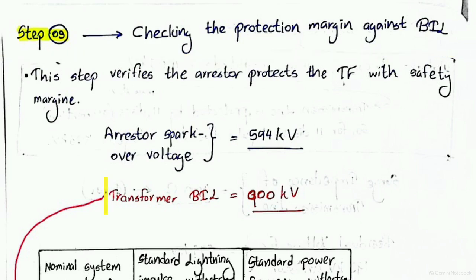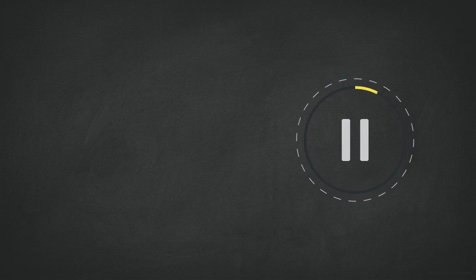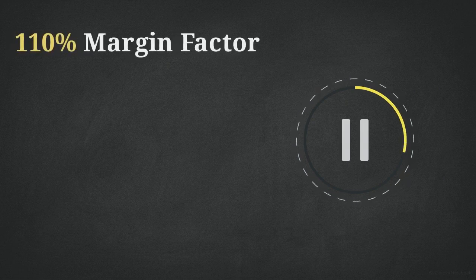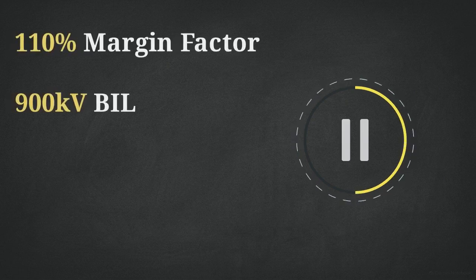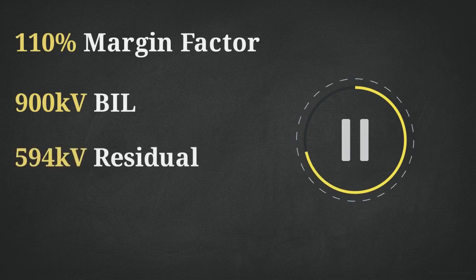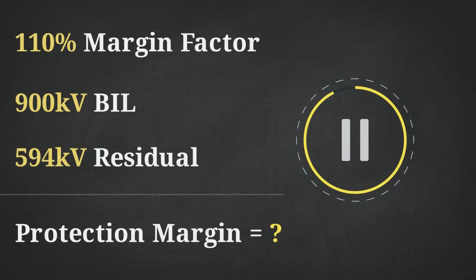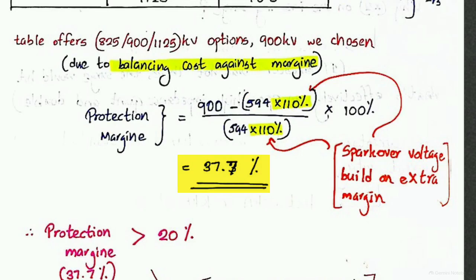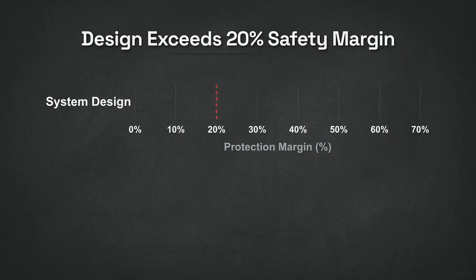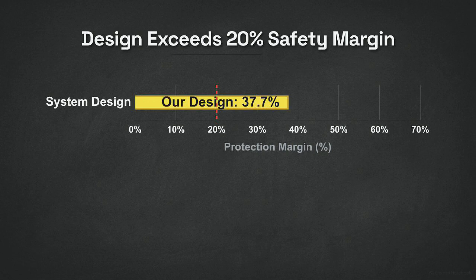For step 3, we calculate the protection margin. We need to guarantee that the transformer's 900 kilovolt basic insulation level, or BIL, is safely above the arrestor's residual clamping voltage. Take a moment to pause the video. Use a 110% safety margin factor, the 900 kilovolt BIL, and our 594 kilovolt residual variable to calculate the protection percentage yourself. Running the numbers through the margin equation, we get a final result of 37.7%. Because industry standards require a minimum protection margin of 20%, our 37.7% result verifies that the selected arrestor will successfully defend the transformer.